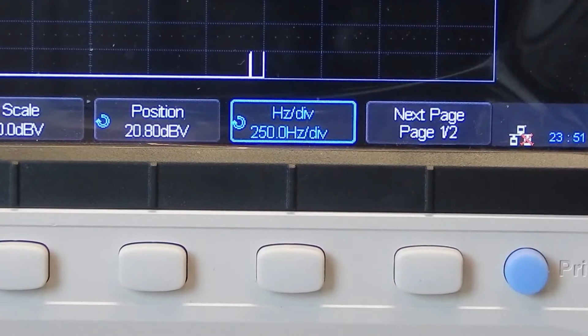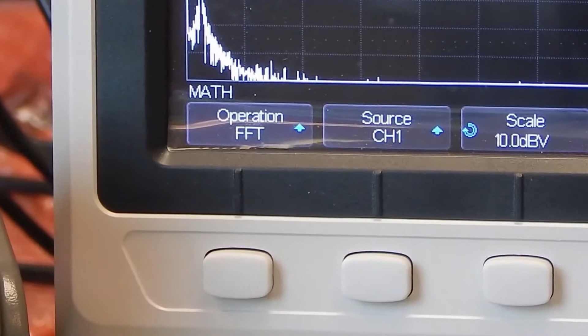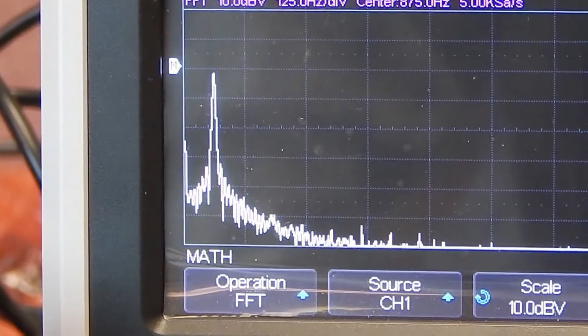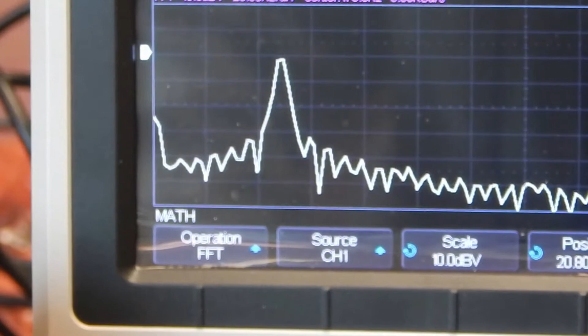Well, this scope has an adjustable hertz per division here. You see we're looking at 250 hertz per division. But if we're looking at a 60 hertz sine wave, obviously we need to probably get in closer. So let's choose that, and let's see what happens here. We'll jump down to 125, and sure enough, it moved over away from the left edge some. And we can actually go down lower. There's 50 hertz per division. And there's even 25 hertz per division. So that certainly is a nice amount of resolution.